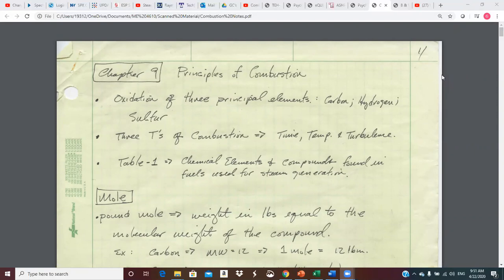The fuel needs to be in a proper consistency too — for example, pulverized coal particle size has an impact. If you're going to burn pulverized coal, you have to bring it up to temperature above the initiation of oxidation temperature and hold it there long enough for complete combustion. You need turbulence with an oxygen source — typically air — for good mixing, so oxygen molecules are present to oxidize the hydrogen, carbon, and sulfur. Sulfur contributes to heat release but also to emissions.